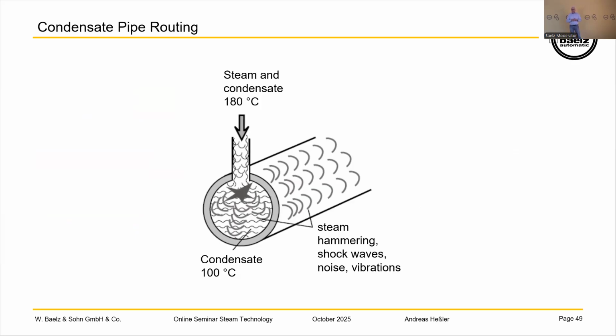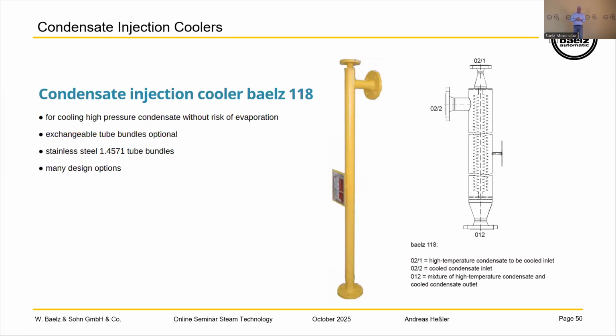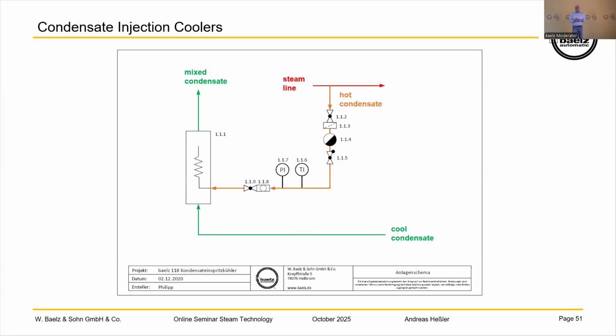That's very critical because you have hammering, shock waves, and noise and vibrations. For this solution, we have our condensate injector cooler BAELZ 118. It is much better, as you will see on the next slide. You will have the hot steam coming from the right side inside the pipe, so it's almost like a heat exchanger with open pipes.